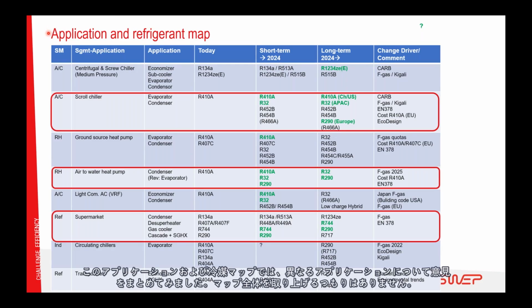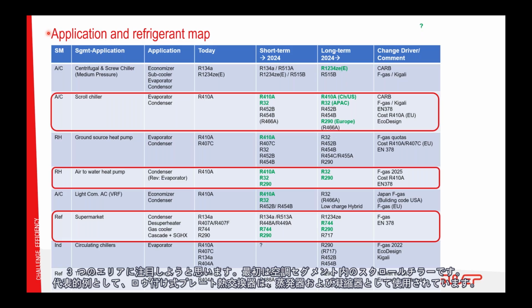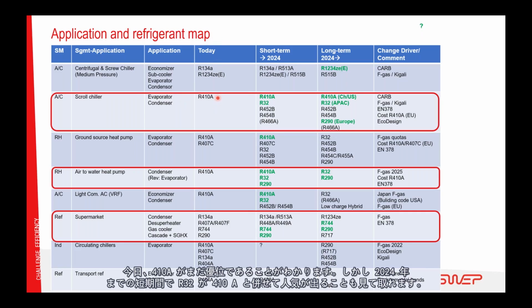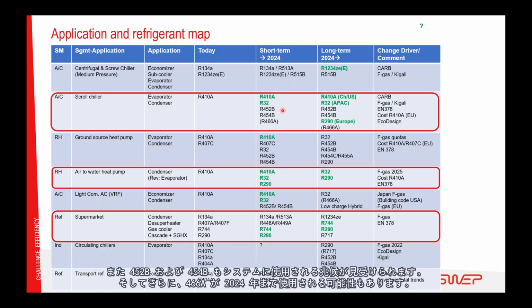In this application and refrigerant map, we have tried to summarize our view on different applications. I will not go through the full map. I will focus on 3 areas here. And the first is scroll chillers within the segment air conditioners. Typically, brazed plate heat exchangers are used as evaporators and condensers. Today, we see that 410A is still dominant, but in the short term, until 2024, we see that R32 will also become popular together with 410A. We see some indications of 452B and 454B also used in systems, and then there is a possibility that 466A will be used until 2024.